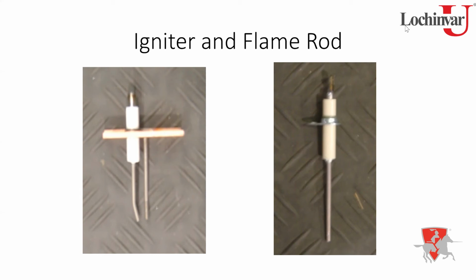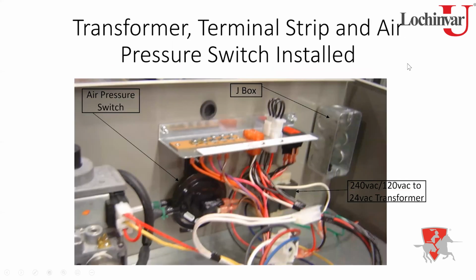All right. So we've got our igniter and a flame rod. So now we start adding the wiring to it. So now we've got all of our main components. Now we're going to start wiring everything up, and we're also going to add this air pressure switch here. All right, so that's a differential pressure switch.